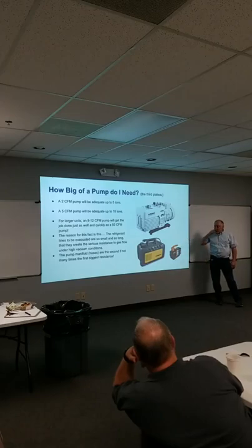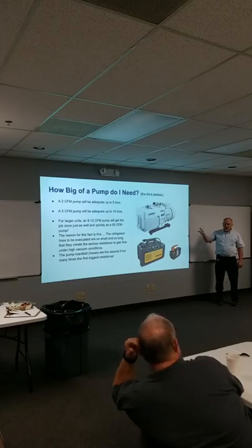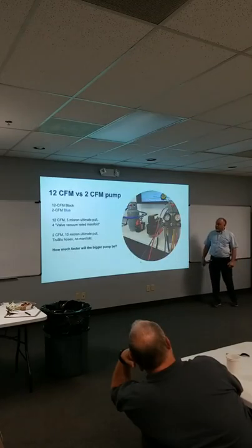I did a chiller. I'll show you. I did a 2,500 chiller a year ago, or 2 years ago. The reason is because the refrigerant lines are so small and so long that creates resistance to gas flow. So there's just no reason to go with a bigger pump. You know, Johnson Controls used to wheel out these huge Welch pumps. I don't know how big some of those things were. They literally took 2 men and a boy to move, and they would hook them up to 1/4 inch hoses, like 6 1/4 inch hoses going everywhere. That was never going to work.